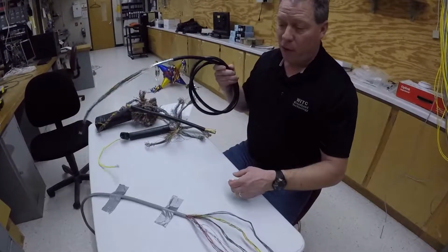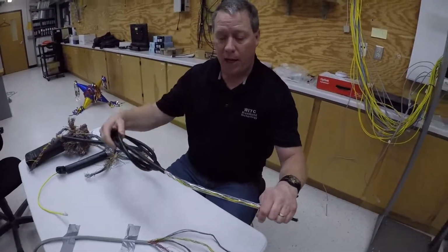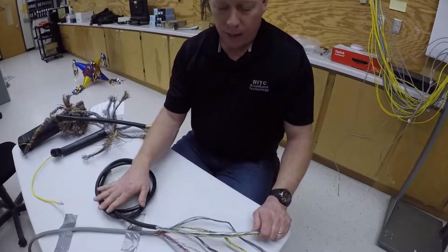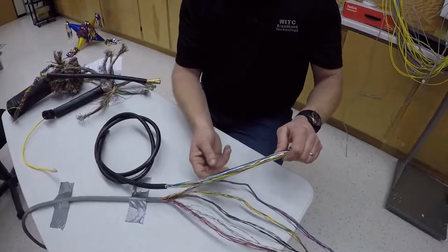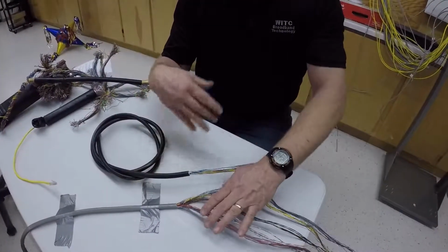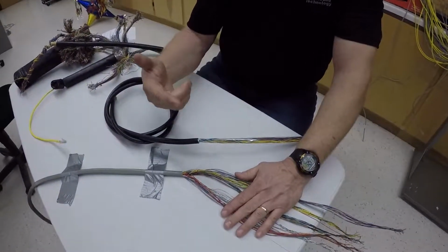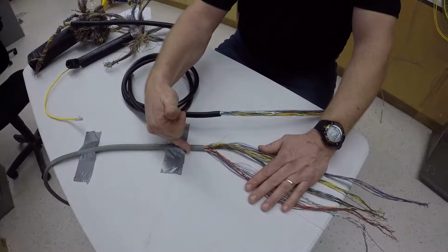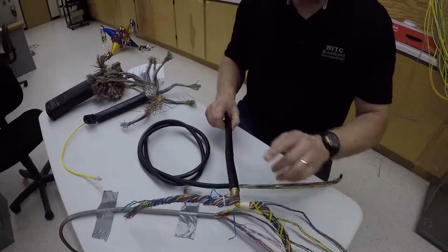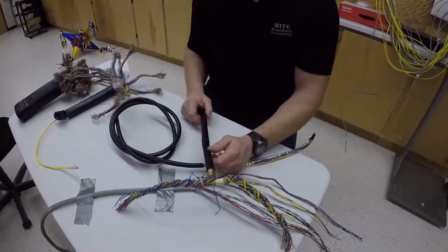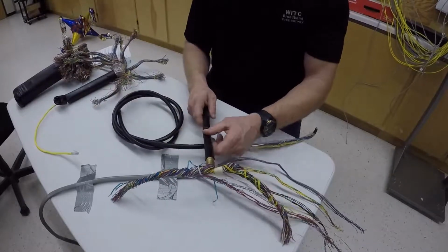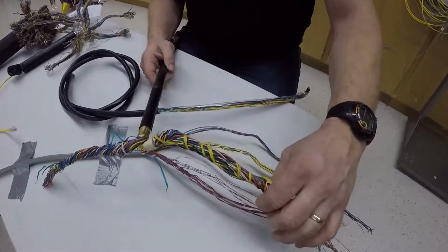If you have more than 25 pairs, this is another type of PE22 aerial cable, and I just want to show how you identify each one of the binder groups. So if you have more than that, you consider your multiples of 25. For example, a 50 pair, like so, you have 2 multiples of 25. The first one is 1 through 25 cable pairs. The second one would be 26 through 50.